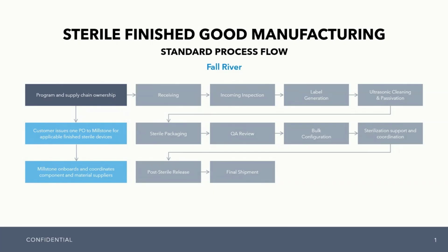And after that, that's when we enter into the clean room for the real value of what Millstone does. That's going to start with ultrasonic cleaning. So it's going to be an ISO class 8 environment where we're going to run through an Alconox clean through a series of rinses. We offer a nitric passivation upgrade if a client requires that for their device. It's going to go through another series of rinses and then through our dryer. Okay. Our product will then go to our ISO class 7 packaging area where we'll perform our sterile packaging operations. So pouch sealing, tray sealing, and if we need to do some assembly prior to going into the packaging, that's where all those operations will occur. Okay.